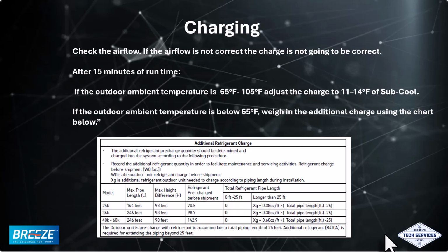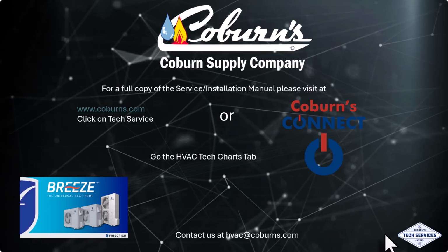If the outdoor ambient temperature is below 65 degrees, you will need to weigh in additional charge using the charging chart below. For a full copy of the service and installation manuals, please visit us at www.coburns.com or our Coburns Connect app. Go to the HVAC Tech Charts tab and download a free copy. You can also contact us at hvac@coburns.com.